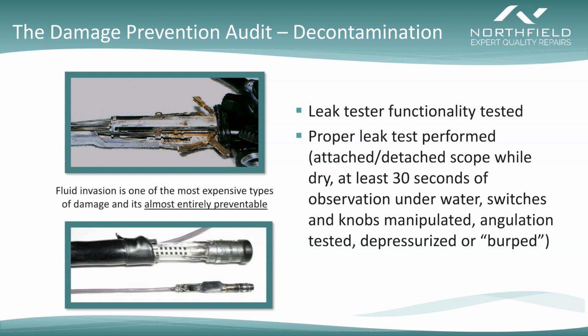After the leak test, we also want to see the scope being depressurized, commonly called burping. Depending on your leak test manufacturer, your leak tester may do the depressurizing or burping itself. But again, you have to know your manufacturer's instructions for both the scope and the leak tester before you can make those determinations.